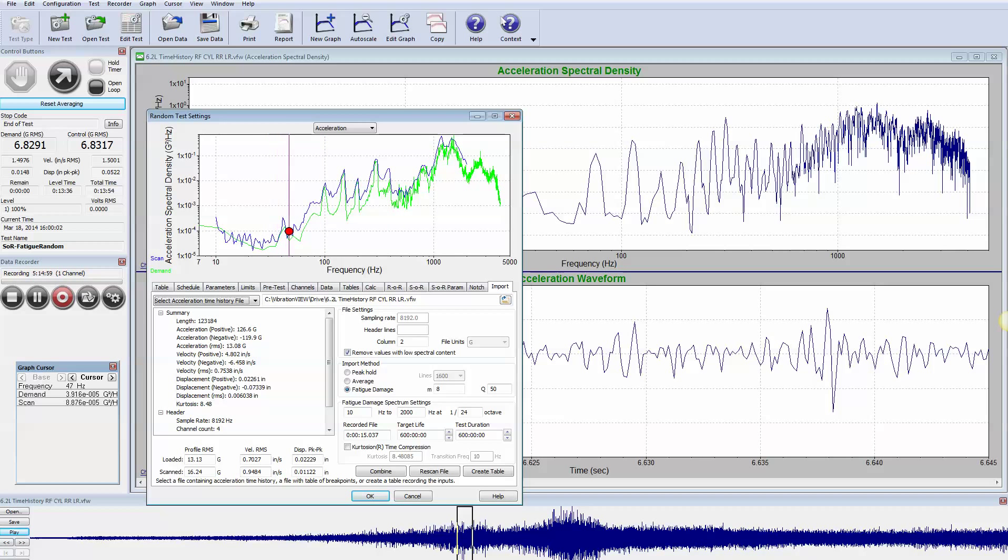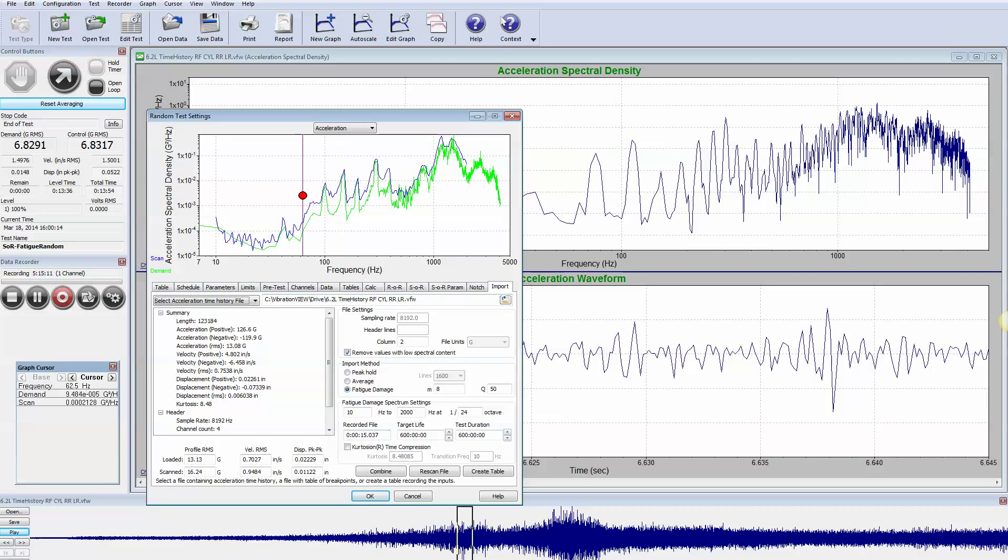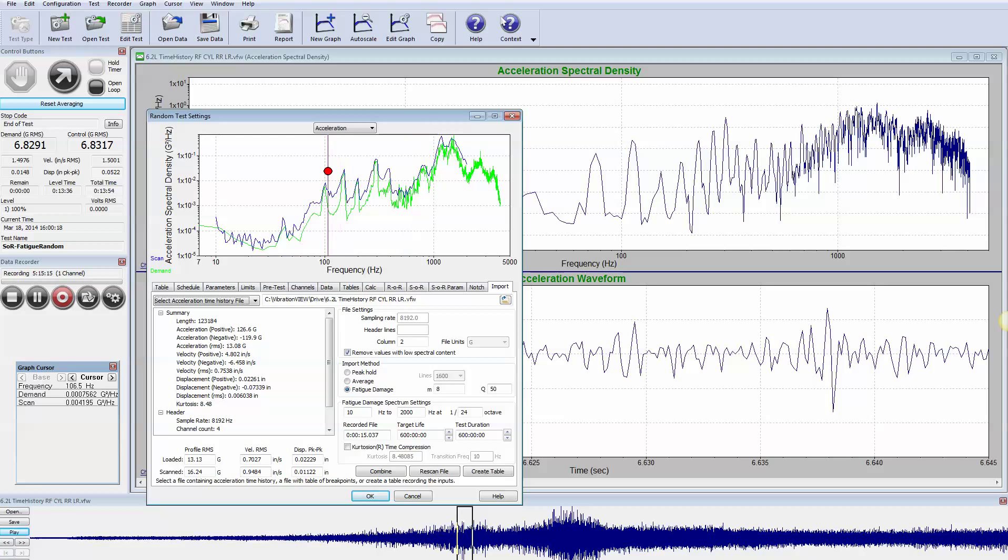The spectrum which we would need to create that damage is shown in this blue line and notice that it's higher at 16.24 G's. So 15 seconds of data equivalently has a higher G RMS level. Where is the additional G RMS coming from?